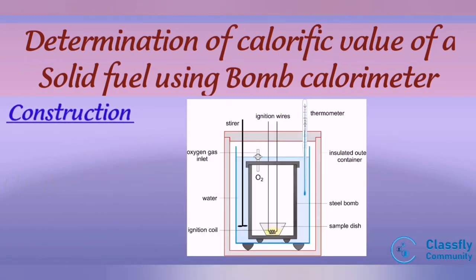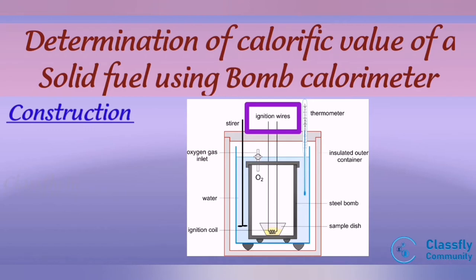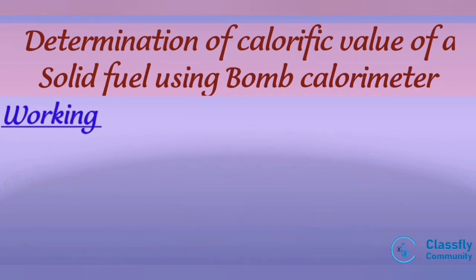Moving on to the construction: in this picture we can see the bomb calorimeter consists of a stainless steel vessel with an airtight lid — this vessel is called the bomb. The bomb has an inlet valve for providing oxygen atmosphere inside the bomb and an electrical ignition coil for starting combustion of fuel. The bomb is placed in an insulated copper calorimeter, which has a mechanical stirrer for dissipation of heat and a thermometer for reading the temperature.